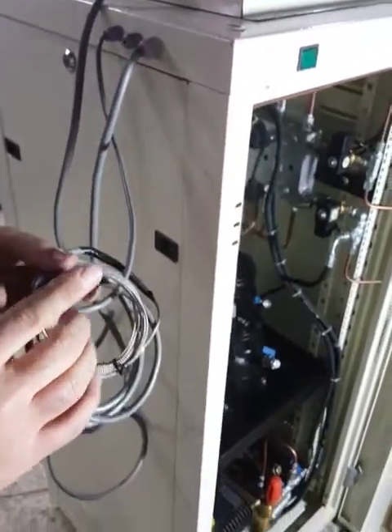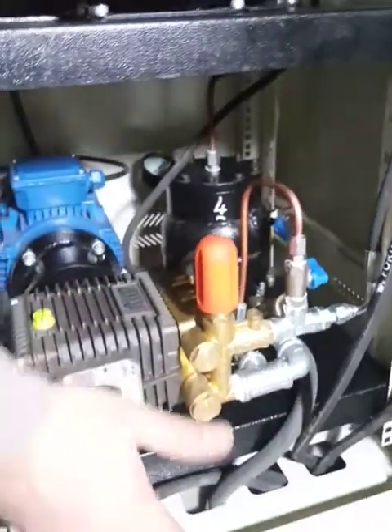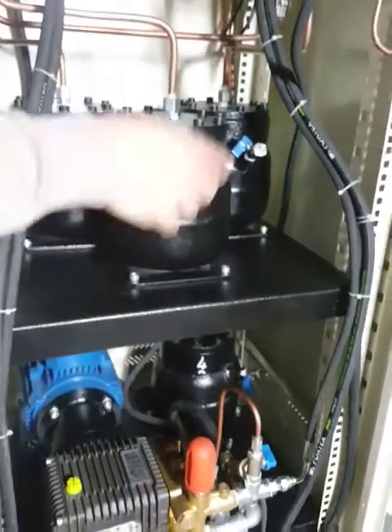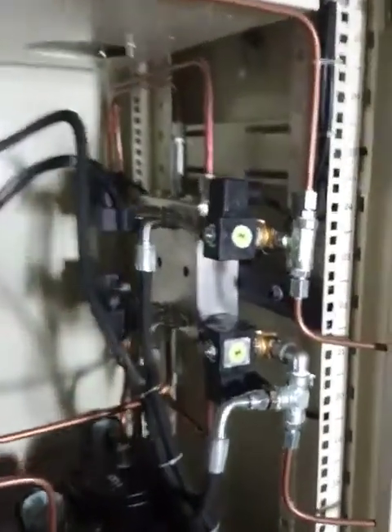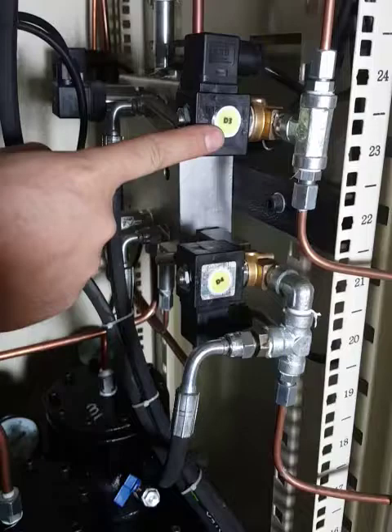As part of the machine hardware, you also have a thermocouple connected to the hot water bath for temperature monitoring. In the bottom side there is the power station, including an electro motor and piston pump. In the next level there is the accumulator bank — four accumulators for the four pressure channels. Above that is the tubing for all four channels, including pressure sensors, needle valves, and pressurizing and drain solenoid valves.